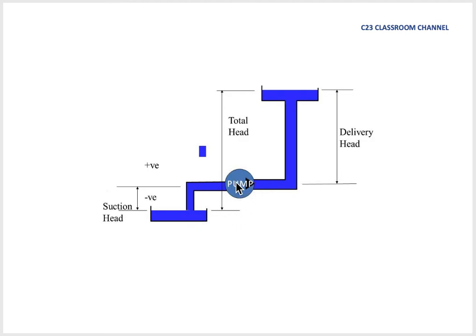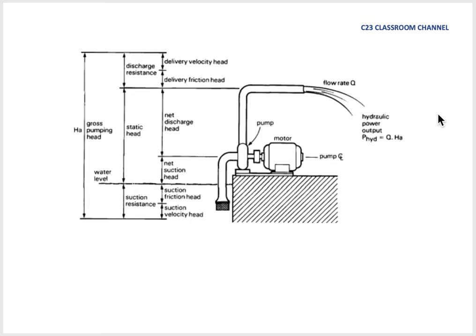And then this is the idea. If we have pump here, the total head is the distance from the suction head here to the delivery head. And when we talk about suction head, this is only the water level here to the center point of the pump. And delivery head is from the center point of the pump to the final water level at the delivery area.